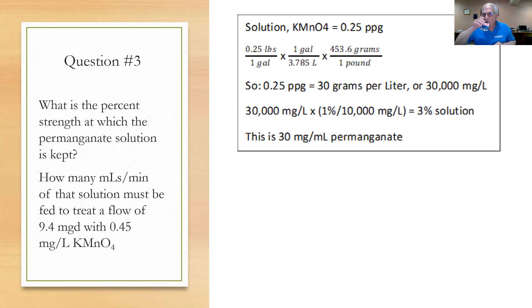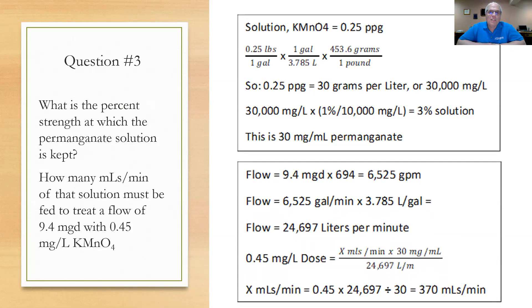For the second part, how many milliliters per minute of the 30 mg/mL (3%) solution is needed to treat 9.4 MGD at 0.45 mg/L? Convert 9.4 MGD to 6,525 GPM by multiplying by 694, then to 24,697 liters per minute by multiplying by 3.785. Setting up the equation: 0.45 mg/L equals X mL/min times 30 mg/mL divided by 24,697 L/min. Solving for X gives approximately 370 milliliters per minute of permanganate solution.